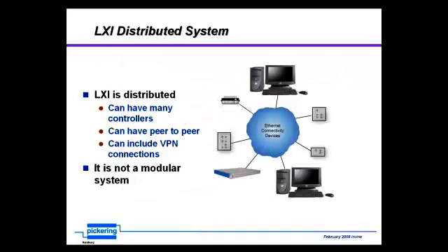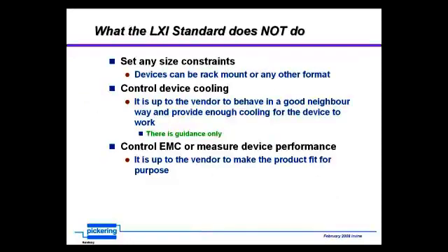The LXI system is a bit different. It's a distributed system, so it can have many controllers, and you can get connections over great distances. One important thing about LXI is that it is not a modular system in the sense of having mechanical or electrical modularity. The LXI standard also has things it doesn't do — it doesn't set size constraints on products, and that's quite important for how we position LXI switching systems.